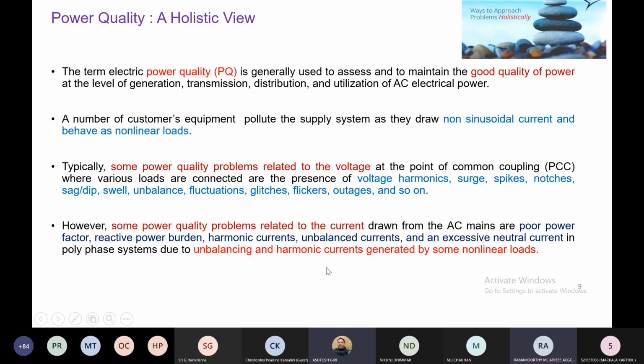These issues relate to power quality problems. In good power quality, there should not be any current in the neutral wire, nor any phase lag between voltage and current waveforms. Voltage and current waveforms must be purely sinusoidal, with no voltage harmonics from the supply side.